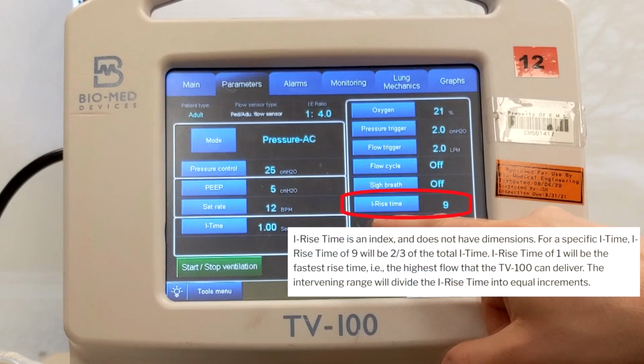The I rise time is an index and does not have dimensions. A specific I rise time of 9 will be 2/3 of the total I time. An I rise time of 1 will be the fastest rise time, i.e. the highest flow that the TV-100 can deliver. The intervening range will divide the I rise time into equal increments.